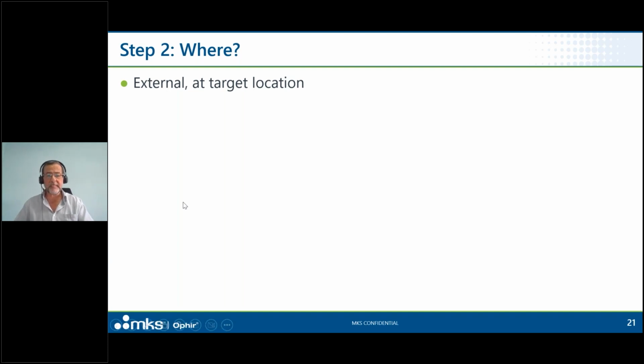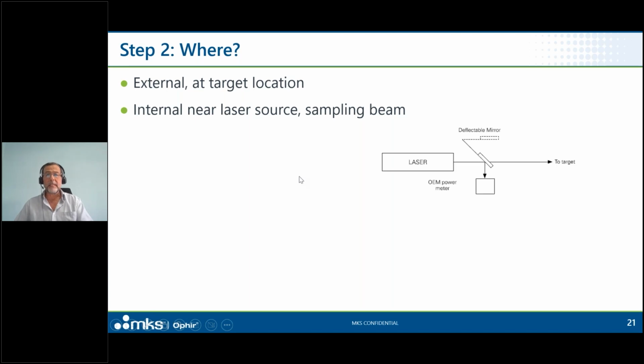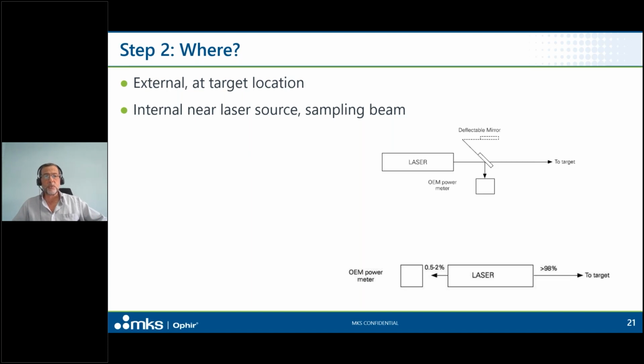So we can implement this in a bunch of different ways. We can implement it as the beam comes out of the laser, periodically put a mirror in there and deflect the beam into a sensor, or permanently put a beam splitter there and continuously measure X% of the laser. In some types of lasers where there's useful rear mirror leakage, I can put a small sensor there, build that into the host system. How do I decide? So there are all sorts of considerations.